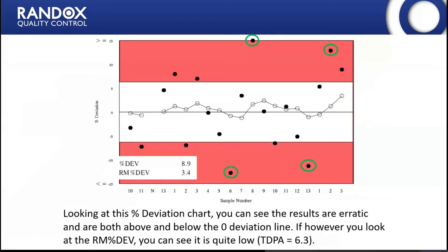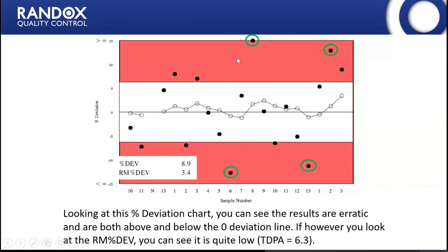There is another instance where using the running mean percentage deviation can be misleading. In this example the running mean percentage deviation for the lab is 3.4 percent, but the percentage deviation of the current sample was 8.9 percent in the red zone. The running mean line always falls nicely within acceptable limits, so if you only looked at the running mean performance would appear good — but the individual results go from low to high, with quite a few falling outside acceptable limits. The running mean needs to be taken in context; used alone the information may be misrepresented based on erratic performance.